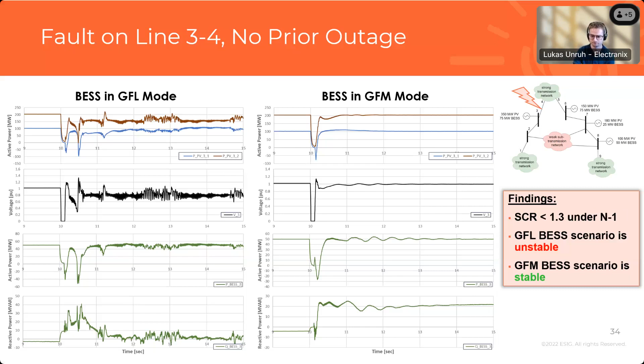This next one that we're looking at is also an N-1 fault. And this one is on that right corridor, and we're removing one of the strong connection points from that cluster. In this scenario, the system strength is a little bit hard to quantify because of the distributed nature of those IBRs, but using a simple WSCR, we would say it's below 1.3. When the batteries were modeled as grid following, we had the response that's on the left here. So we would say this is a marginally passing case, or could be a fail depending on the criteria that's being applied.